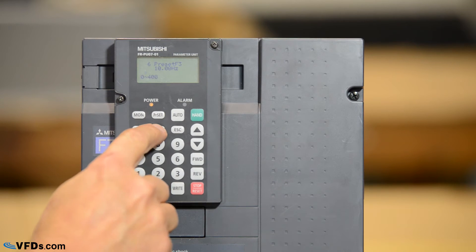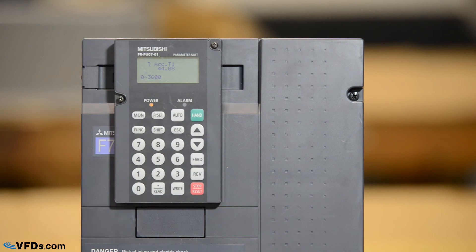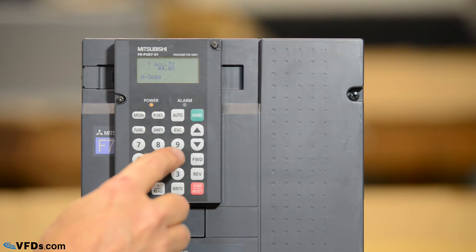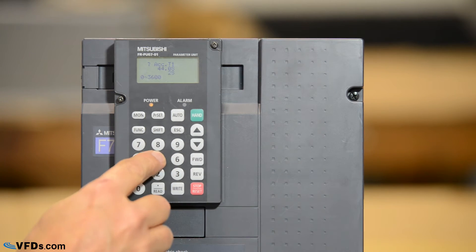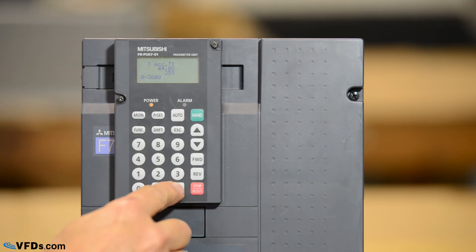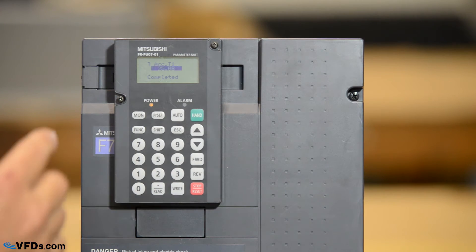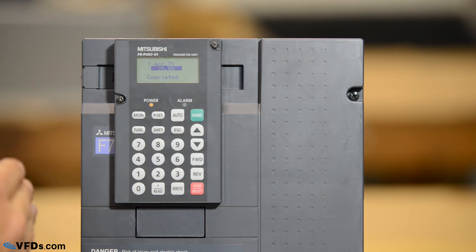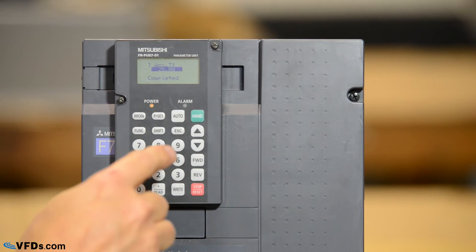So let's press shift one more time and we have our acceleration time. It's set for 44 seconds. I want it to go a little quicker than that so I'm going to set it for 25. 25 right sets the acceleration time for 25 seconds. Now it will go from 0 to 60 hertz in 25 seconds.